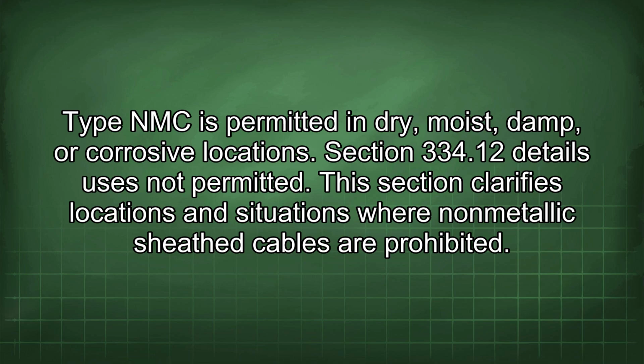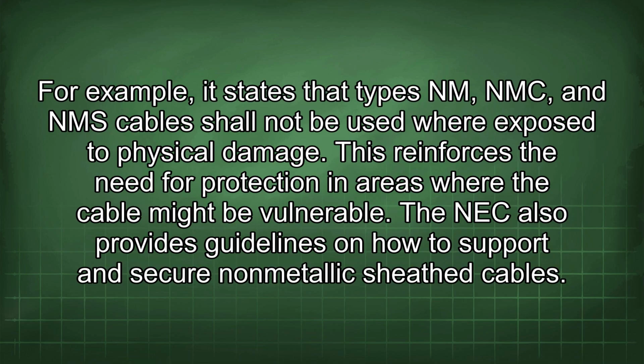Section 334.12 details uses not permitted. This section clarifies locations and situations where non-metallic sheathed cables are prohibited. For example, it states that types NM, NMC, and NMS cable shall not be used where exposed to physical damage. This reinforces the need for protection in areas where the cable might be vulnerable.